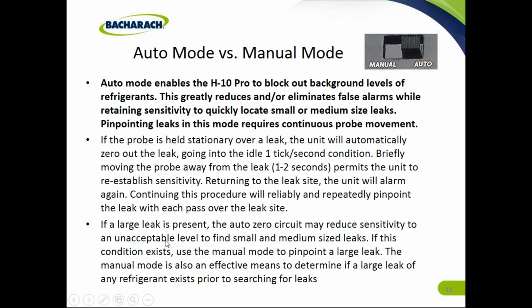If the probe is held stationary over a leak, the unit will automatically zero out that leak and go into an idle, 1 tick per second condition. Briefly moving the probe away from the leak, 1 to 2 seconds, permits the unit to re-establish sensitivity. Returning to that leak site, the unit will then alarm again. Continuing this procedure will reliably and repeatably pinpoint the leak with each pass over the leak site.